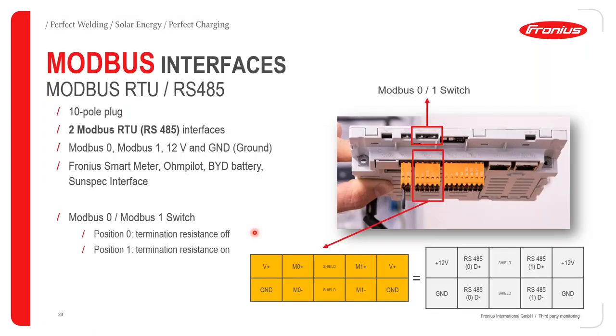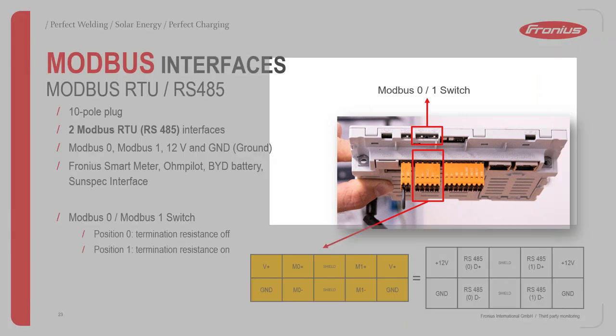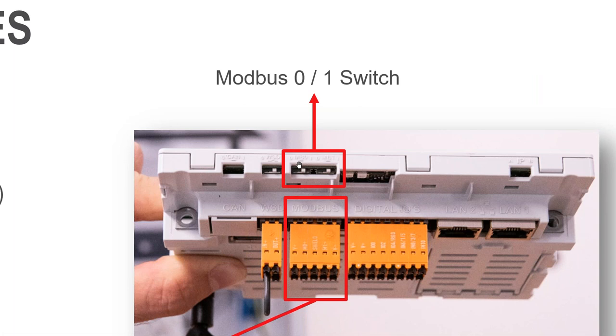One long push is for quitting service messages and for activation and deactivation of the key lock. Looking at the Modbus interfaces: we have a 10-pole plug with two available Modbus ports. To use any of the Modbus ports, you must activate it using the DIP switches — switching from position 0 to position 1.